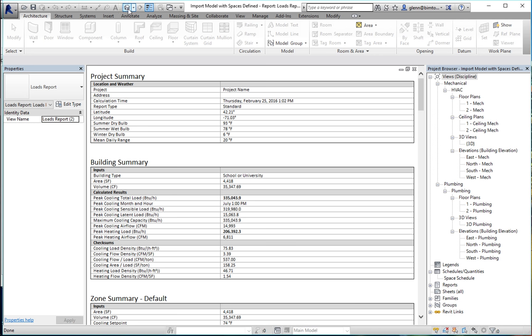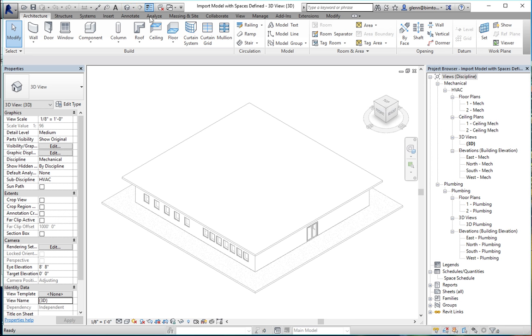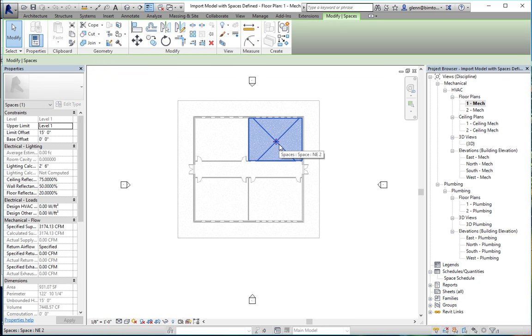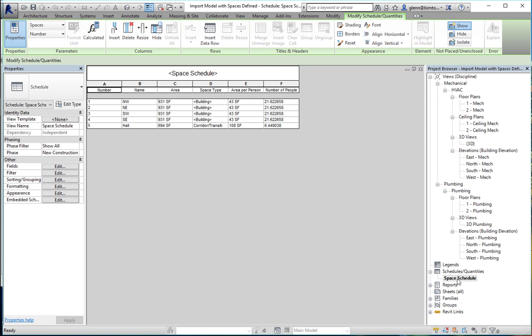Looking at this building in 3D, it's a simple little building with several different spaces. These spaces are defined going from floor all the way up to roof level. Each space has an occupancy associated with it. I have four classrooms — northwest, northeast, southwest, southeast — each with a certain square footage, building occupancy set to school or classroom, about 43 square feet per person and around 21 people in each room. There's also a corridor with fewer people due to a higher area per person.